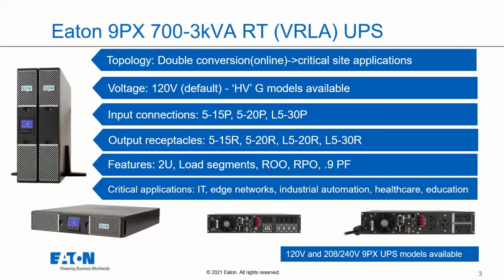Other features include the ROO, or remote on-off, remote power off, and output relay ports providing increased controls. The remote on-off port allows you to remotely shut down the UPS and restart automatically when the remote contact is reset, which is great for light industrial applications. And then, of course, the 9PX also has a 0.9 power factor and up to 94% efficiency in online mode, cutting energy usage and costs.